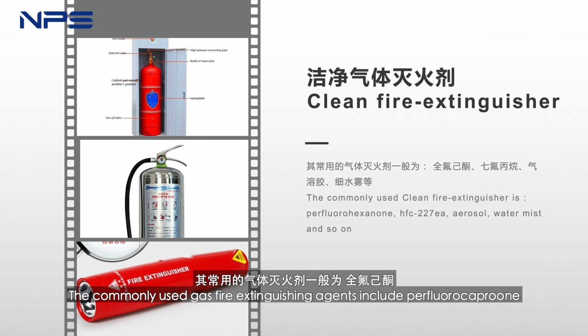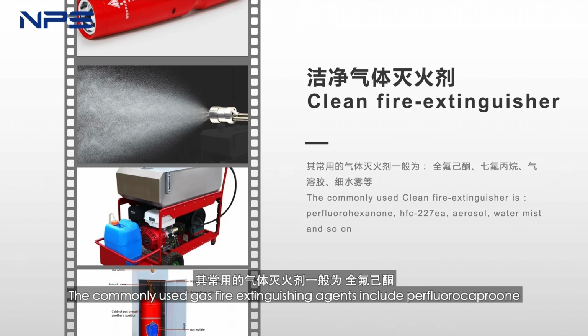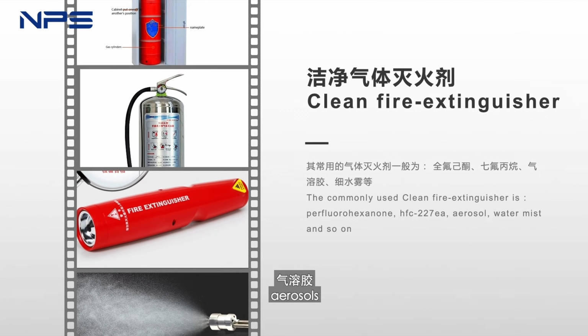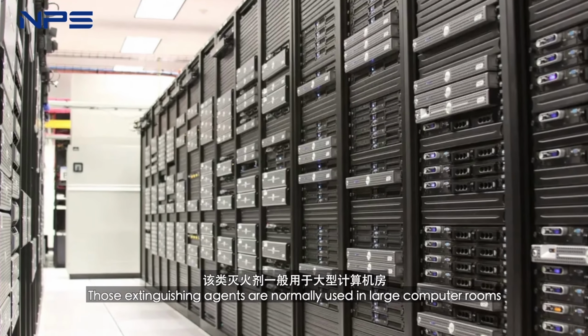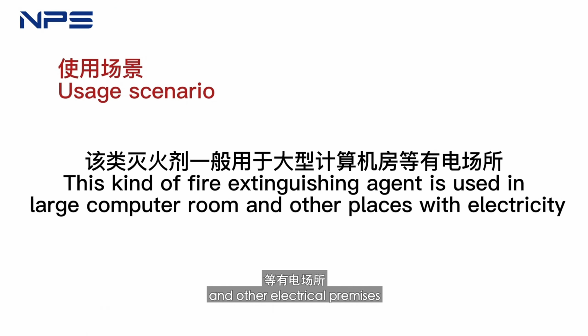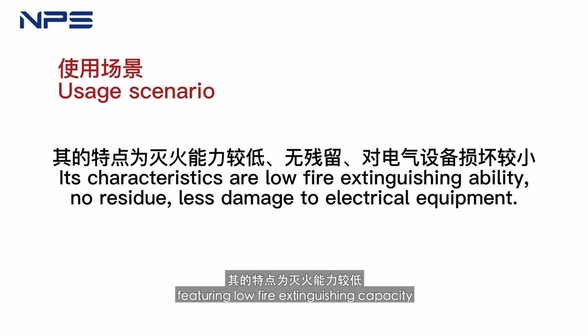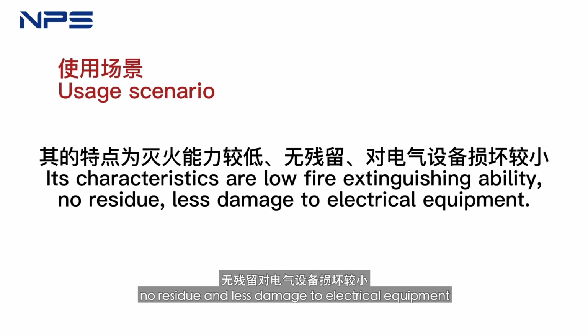The commonly used gas fire extinguishing agents include perfluorohexanone, heptafluoropropane, aerosols, water mist, etc. Those extinguishing agents are normally used in large computer rooms and other electrical premises, featuring low fire extinguishing capacity, no residue, and less damage to electrical equipment.